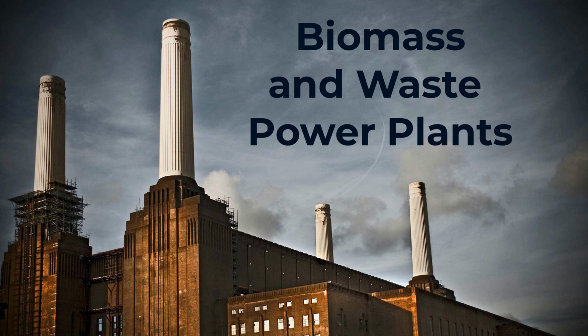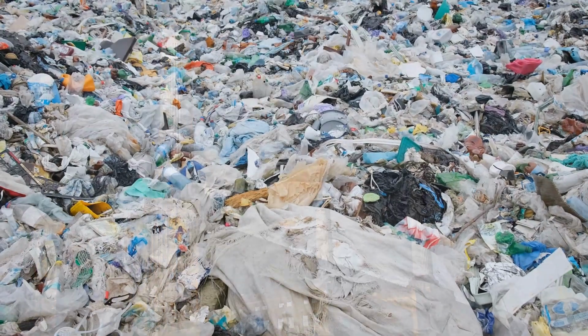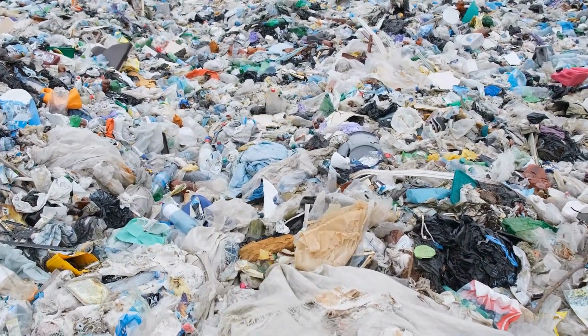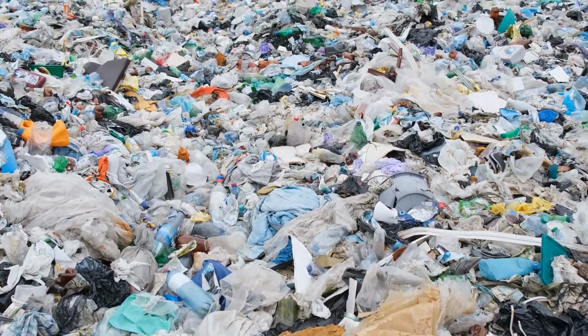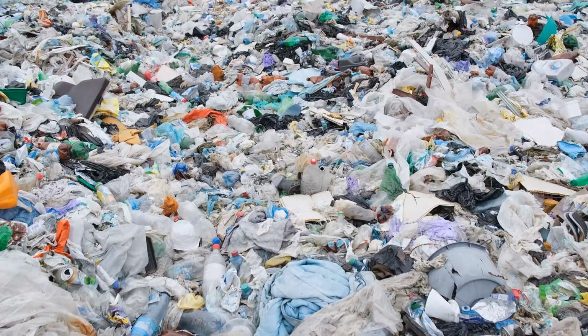In addition to that, there have been cases in the past where people have disposed of explosives, bullets. These have then been burnt on site within the boiler or within an incinerator, and that then has caused damage to the equipment and in some cases loss of life. With a biomass plant, it's quite easy to spot if someone has put explosives, bullets or radioactive material into a truck that's full of tree bark. However, with waste, this is not the case. It's very difficult to separate out the various parts of the fuel.